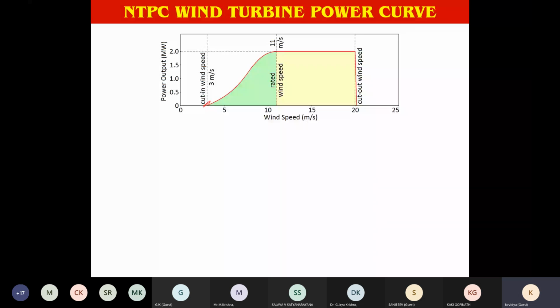So normally, in our country, the cut-in wind speed is typically 3, or 2.5 or 3.5, typically 3 meters per second. Because in NTPC, we have two different makes of wind turbine, cut-in wind speed is 3 meters per second. And after 3 meters per second, with the increase in wind speed, wind turbine output increases. And by about 11 to 12 meters per second, it reaches its full capacity, for example, 2 megawatt output. This is basically the data sheet of the NTPC wind turbine, 2 megawatt output. And its nominal or rated wind speed is 11 meters per second. That means at 11 meters per second wind speed, the NTPC wind turbine reaches its full capacity of 2 megawatt. Now, we cannot expect that wind speed will go only up to 11 meters per second.